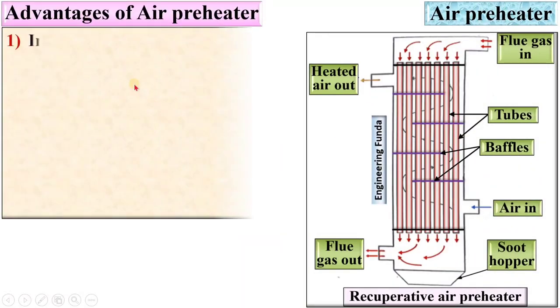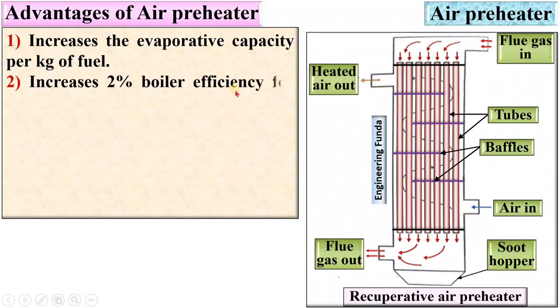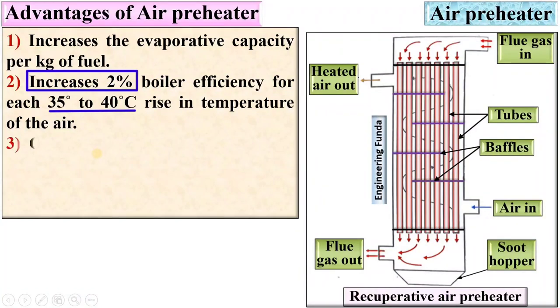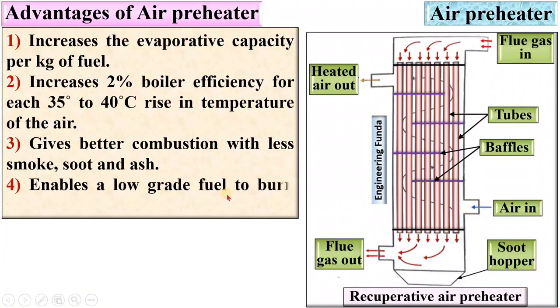Advantages of air preheater: it increases the evaporative capacity per kilogram of fuel. It increases boiler efficiency by 2% for each 35 to 40 degree Celsius rise in temperature of the air. It gives better combustion with less smoke, soot, and ash. It enables low-grade fuel to burn with less excess air.